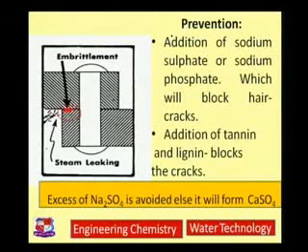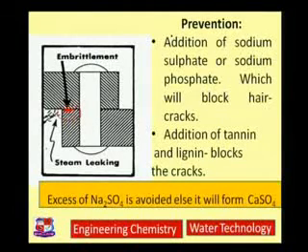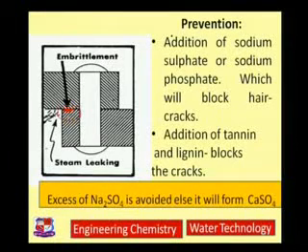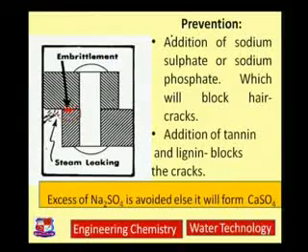To prevent caustic embrittlement, we should add sodium sulphate or sodium phosphate in place of sodium carbonate, as these will block hair-like cracks. Besides that, we can use tannin and lignin to block the cracks and avoid contact between the boiler material and NaOH. However, we must be cautious — if excess sodium sulphate is used, it may form calcium sulphate, which may lead to scale formation. So we should be very cautious while using preventive measures for caustic embrittlement.